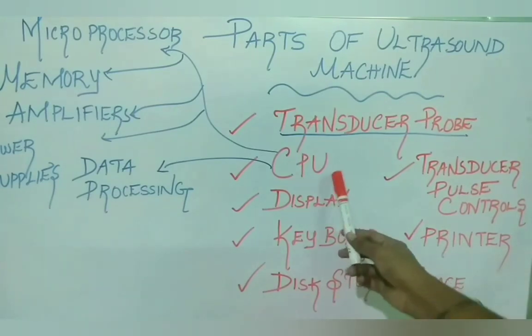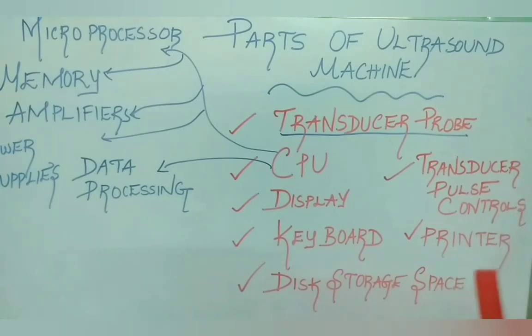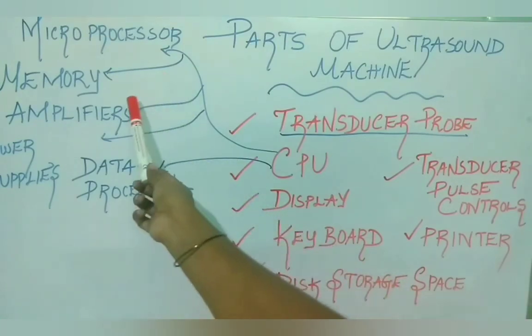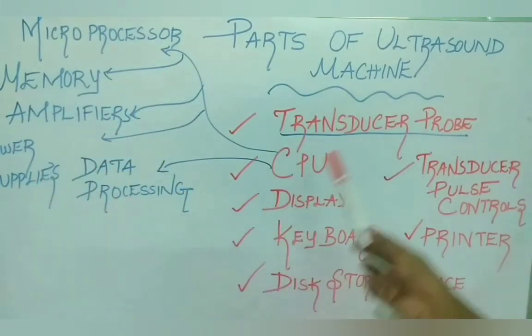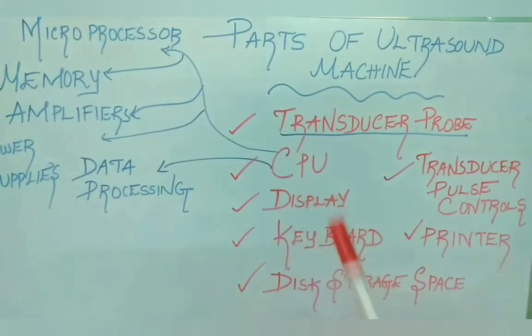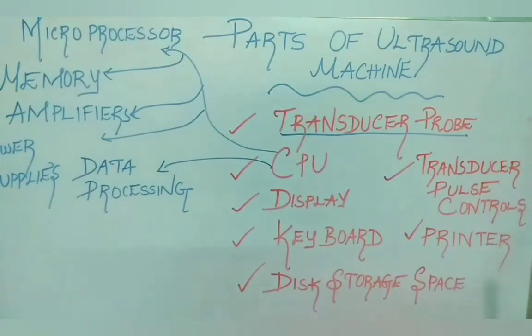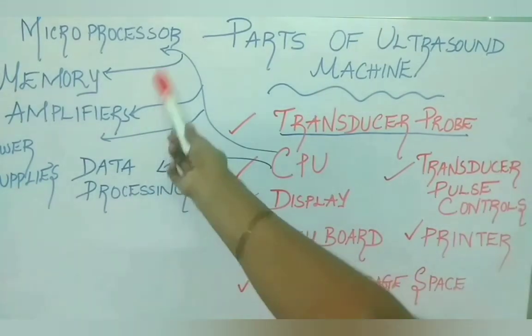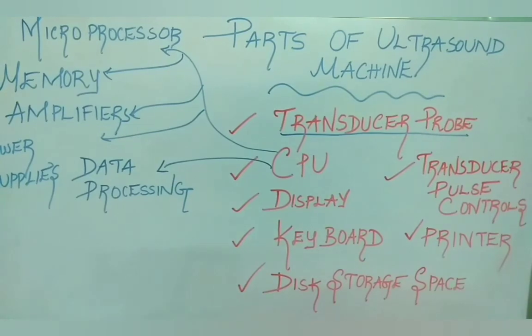Till now we studied about transducer probe. Now we are going to study about CPU or central processing unit. It is the brain of the ultrasound machine. It is basically a computer and it contains microprocessor, memory, amplifiers, power supplies for transducer probe and microprocessor. Microprocessor is a miniature electronic device that contains very small components like transistors, resistors, diodes that work together. Computer memory is the storage space in the computer where data is to be processed and the instructions required for processing are stored.